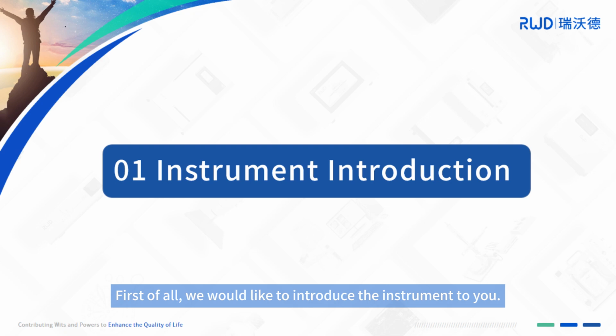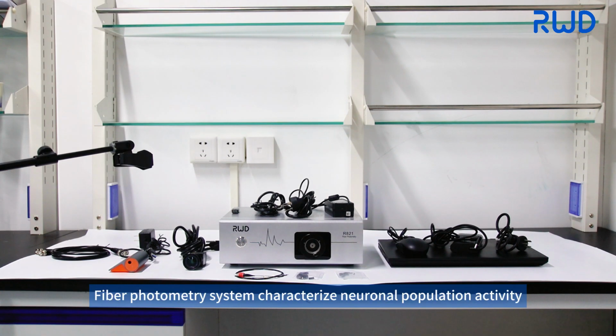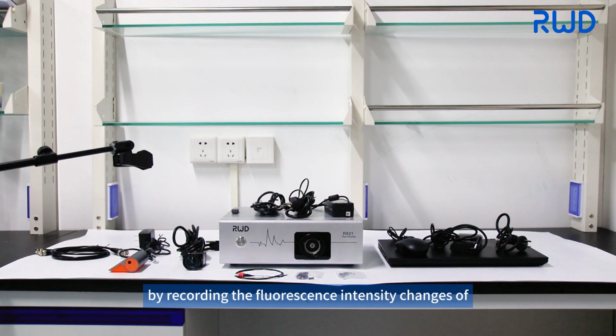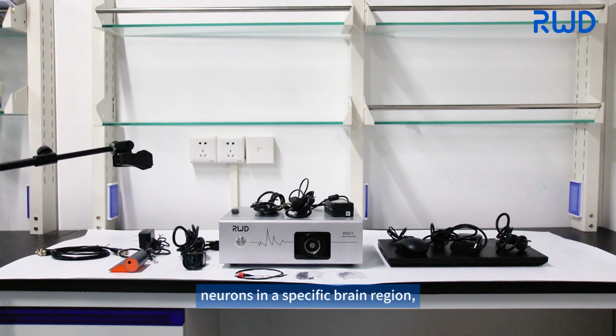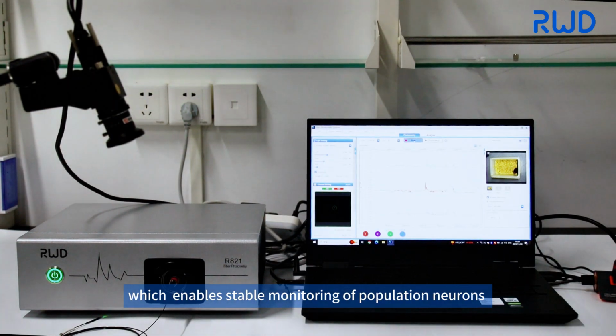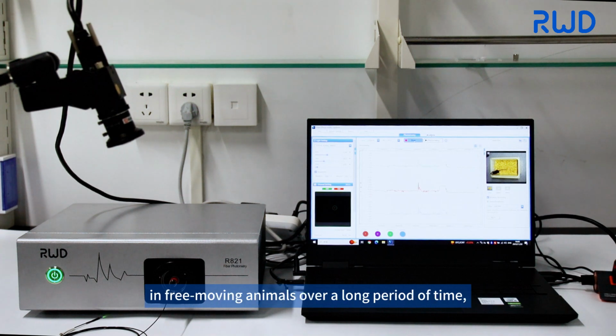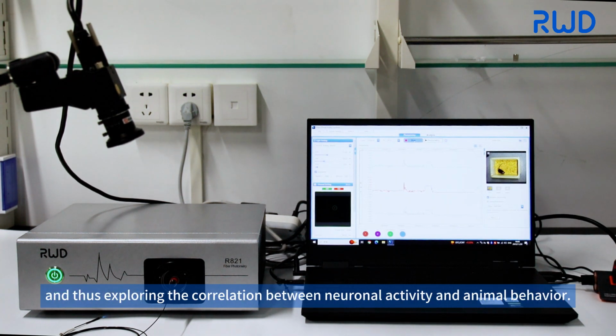First of all, we would like to introduce the instrument to you. Fiber photometry systems characterize neuronal population activity by recording the fluorescence intensity changes of neurons in a specific brain region, which enables stable monitoring of population neurons in free-moving animals over a long period of time, and thus exploring the correlation between neuronal activity and animal behavior.